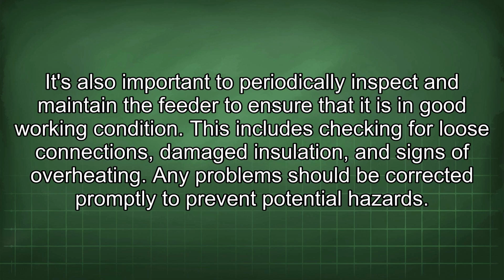It's also important to periodically inspect and maintain the feeder to ensure that it is in good working condition. This includes checking for loose connections, damaged insulation, and signs of overheating. Any problems should be corrected promptly to prevent potential hazards.